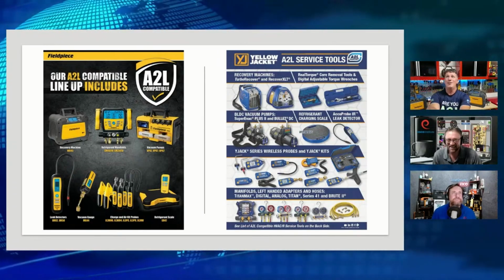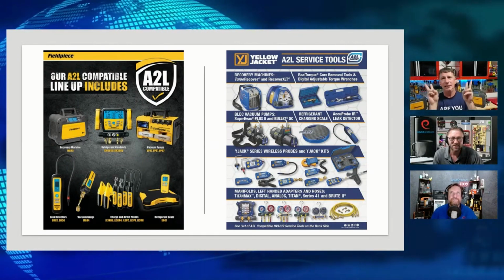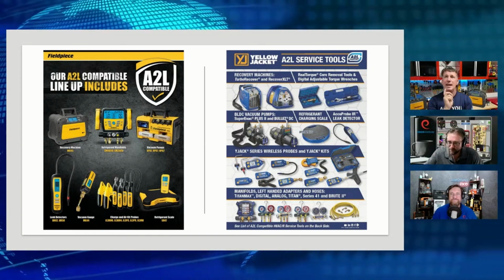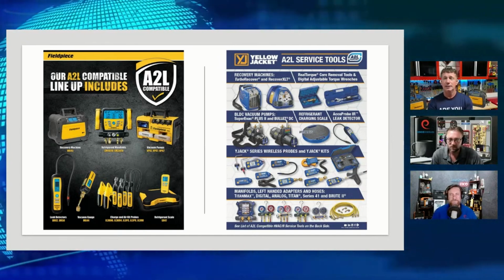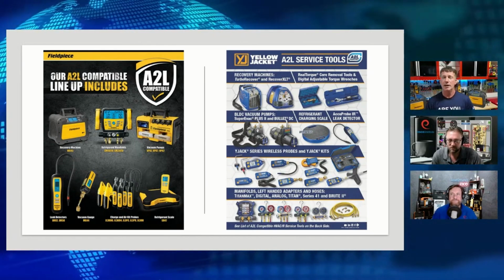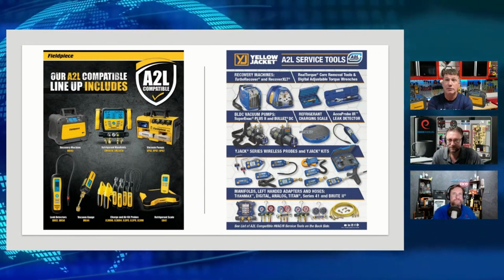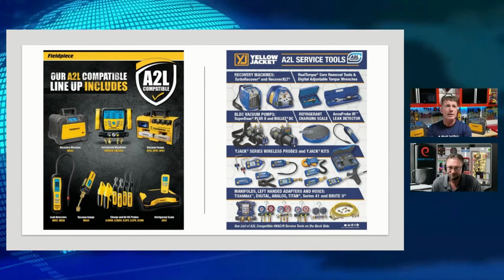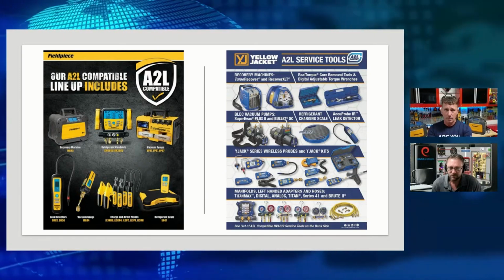All right, so let's talk about what ones are being relabeled, branded A2L compatible. Remember, it's not a certification. It is a standard that has been established by the manufacturer to validate that it is safe to use in the environment. Some have been tested, certified, some have not. So we're really relying on our brands to validate that they've been manufactured with these design parameters. And we see a lot of that. So you're going to see a lot of literature, and most of it's already out there, showing the different pieces of equipment and tools that a manufacturer will recommend as being A2L compatible.